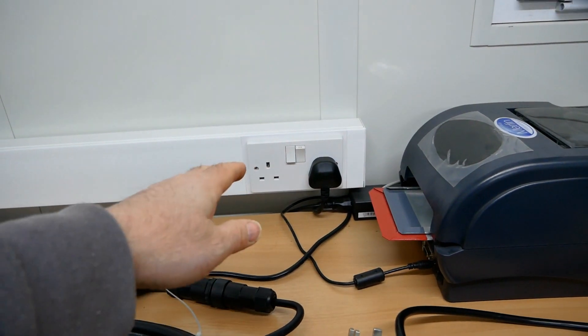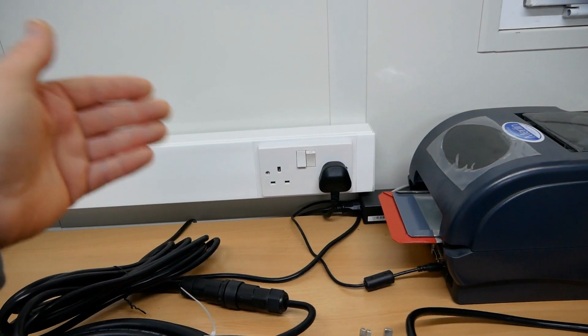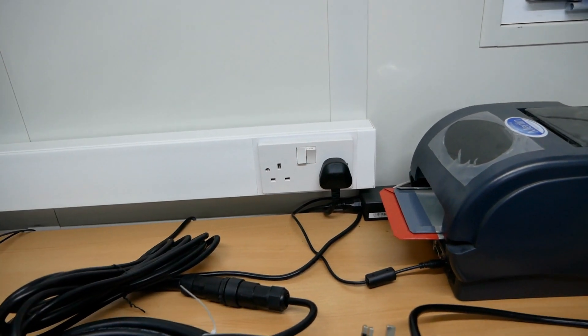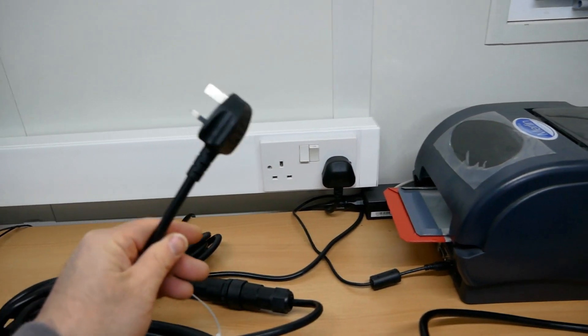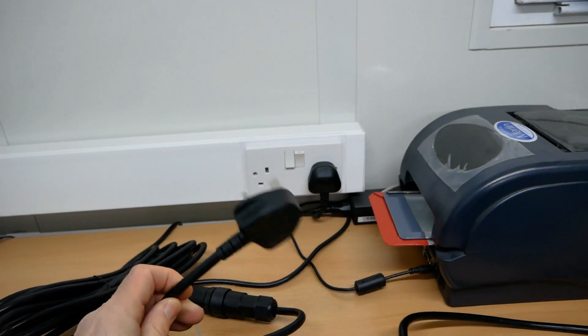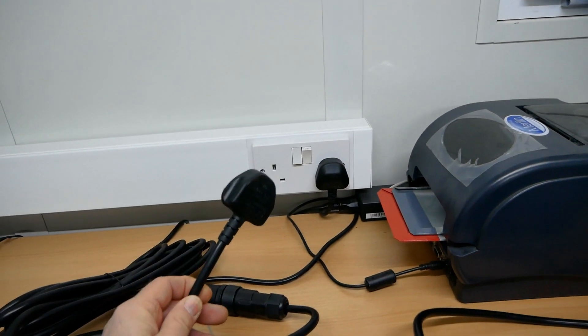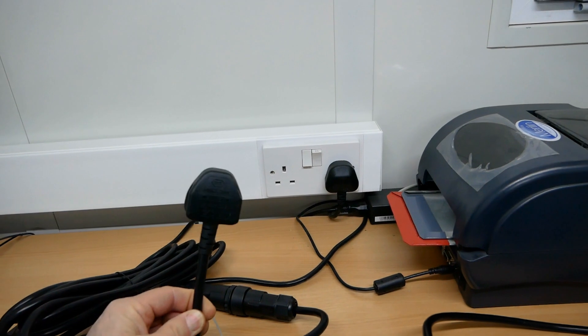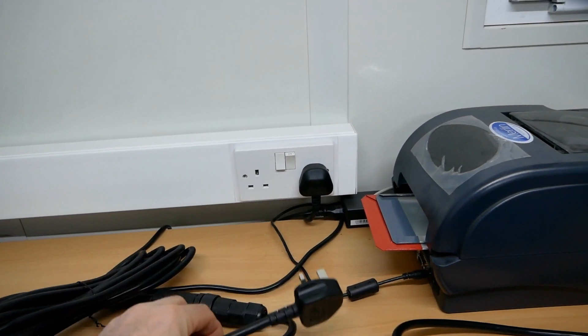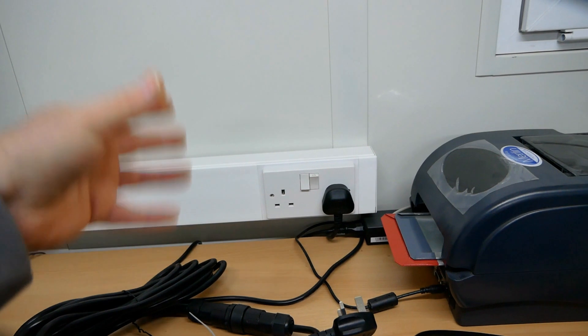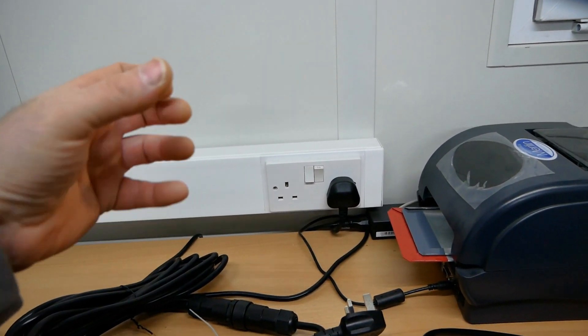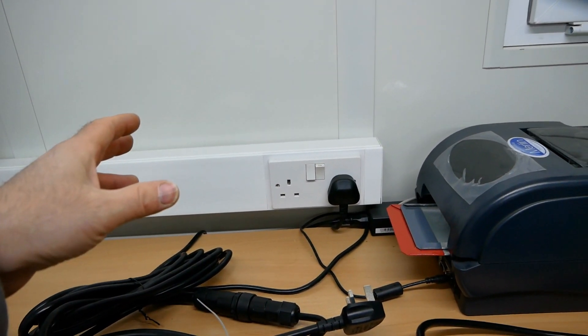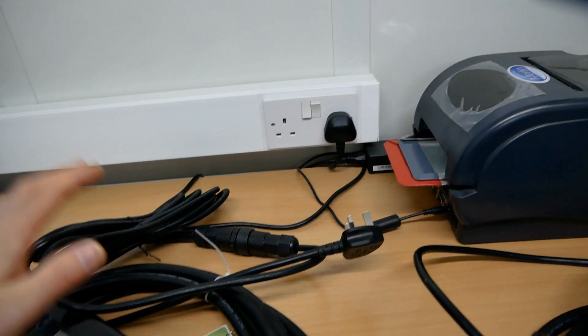Maybe you could put a kettle in there and boil a kettle—that's only going to draw power for two minutes. It's not going to highlight the problem. You stick something like a granny cable on, it might only be 10 amp, it's still within spec. If it was only charging for five minutes you wouldn't see the problem, but because it's charging for 10 hours, that's when the overheating arises and it will just highlight problems that have always existed that you never knew about.